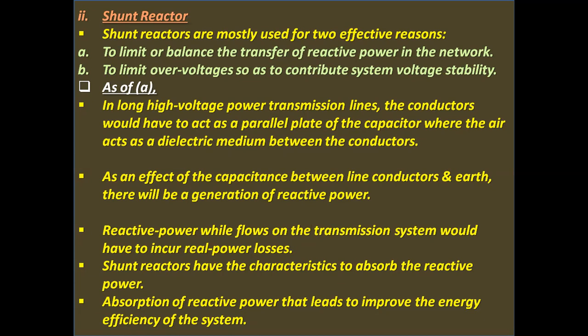As an effect of the capacitance between line conductors and earth, there will be a generation of reactive power. Reactive power, while flowing on the transmission system, incurs real power losses. Shunt reactors have the characteristic of absorbing the reactive power. Absorption of reactive power leads to improved energy efficiency of the system.